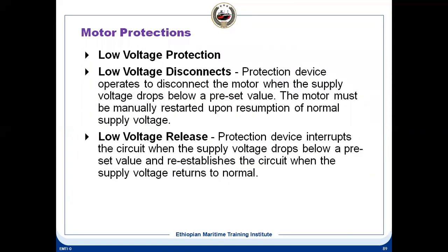Now the other protections, like low voltage protection. A protection device operates to disconnect the motor when the supply voltage drops below a preset level. That is low voltage protection. It is not necessary that you will find all of these protections in a starter, but these are the general protections. The motor must be tripped when the voltage drops to a certain level. This is low voltage protection, and also low voltage release. The protection device interrupts the circuit when the supply drops below preset values.